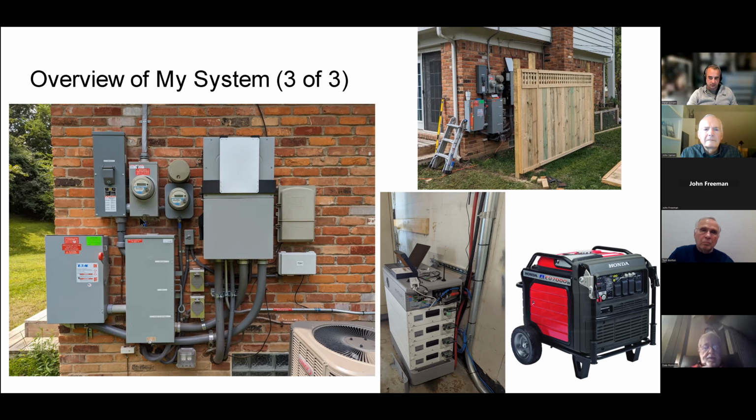So it goes 200 amp in through this transfer switch into the inverter right here. I have a kind of chintzy cover just so I don't have UV damage on the LCD panel until I get a proper cover on it. But the important thing that makes this so robust and awesome is that the whole DTE service of 200 amps is managed by the hybrid inverter system. I'm not doing a line side tap into my breaker panel. So it manages everything. What you get with this is like a UPS system for your whole house, like an uninterruptible power supply.